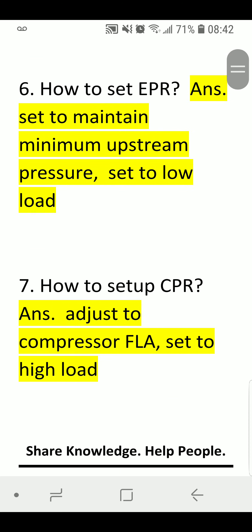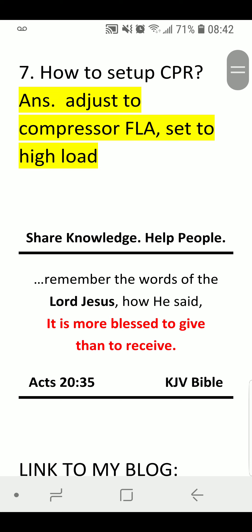How to Set EPR. Answer: Set to maintain minimum upstream pressure; set to low load. How to Set CPR. Answer: Adjust to compressor full load amps (FLA); set to high load.